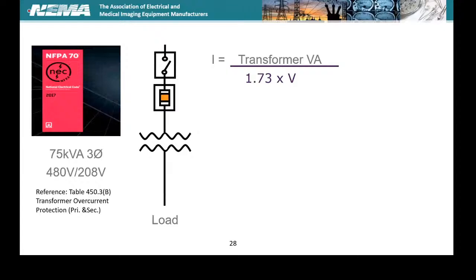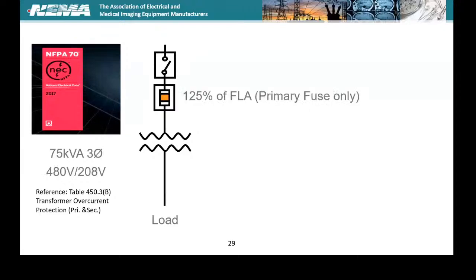We got a primary current of 90 amps. We've got the total transformer VA. We've got a formula to use to come up with that. And we've got a secondary current of 208 amps. And the first one, we have 125%, primary fuse only. So in that case, we got a 90 amp full load current on the primary, multiply it, we get that 112.5, and where'd we go?